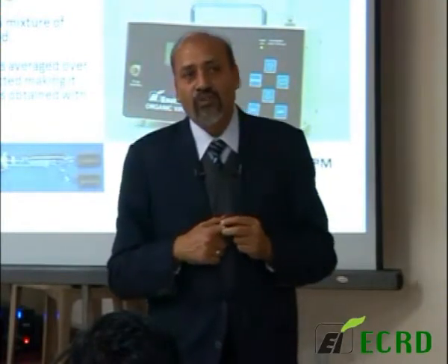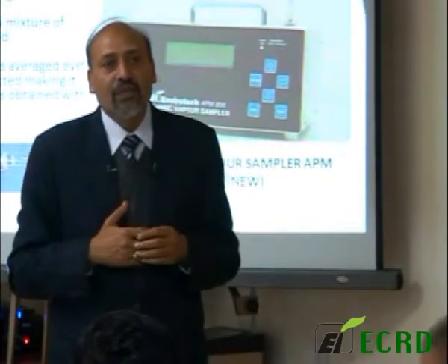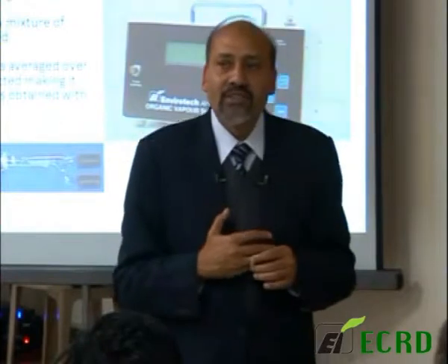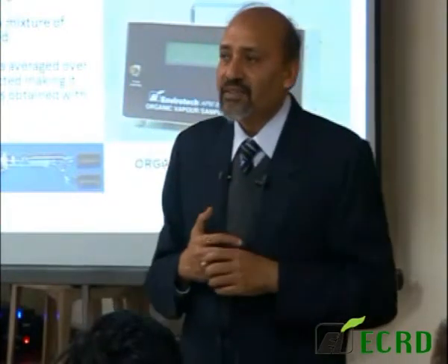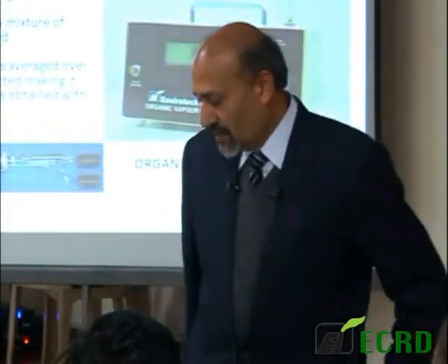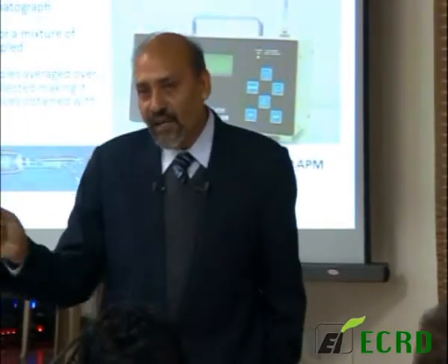And this idea we got from some of the CPCB scientists who were helping us to evaluate this system, and it has now been incorporated in the electronics of the system, which has a built-in real-time clock, and it helps you to set up a compositing sampling time.